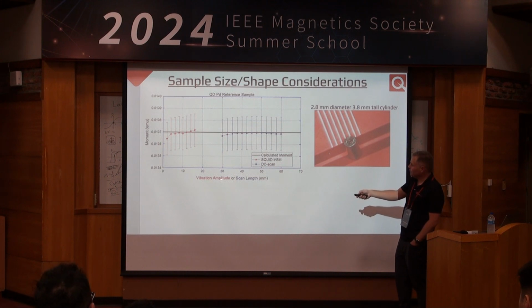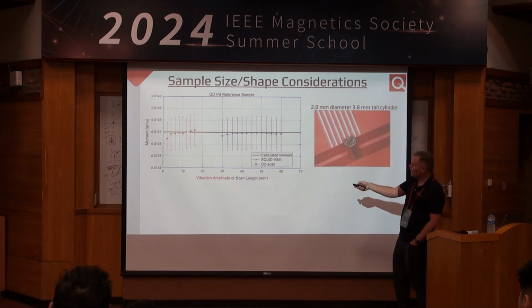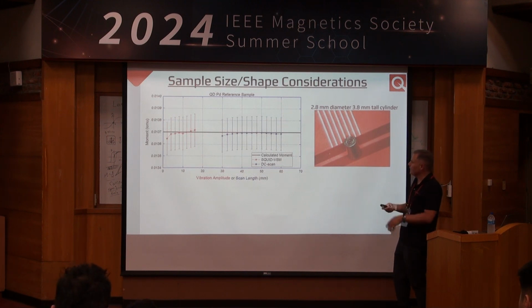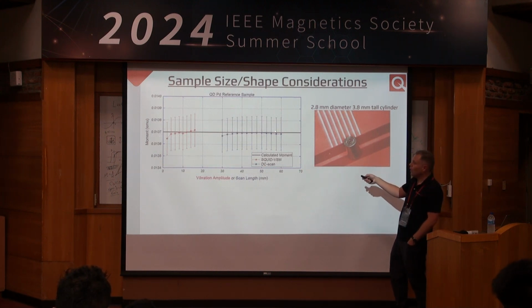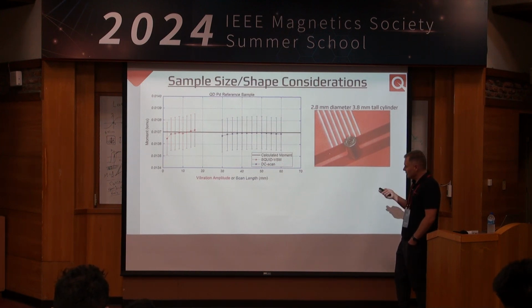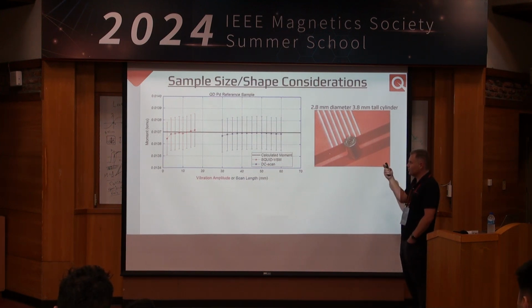The moment as a function of vibration amplitude is shown here in red. This is for that SQUID VSM mode, or the DC scan here. This would be the scan length. So we see that they agree with one another. Notice the scale here, very tight. There's a little bit of scatter here, but it's well within our 1% accuracy specification. But it's this way because we actually calibrated the system to look like this.